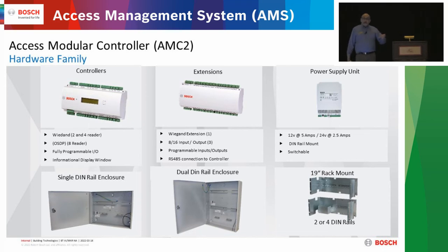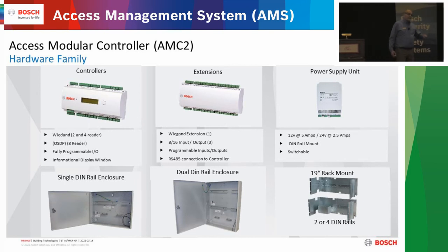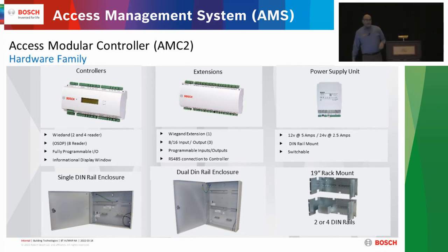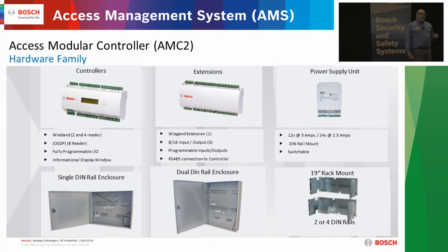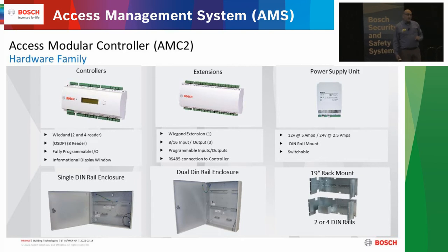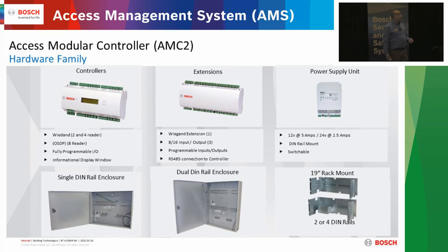On my outputs, they're not dedicated — I program them for how I want them to fire. The really cool thing is I can take a jumper on the back of this board and flip that jumper for any individual output, making that dry contact wet. The power supply is a 12-volt, 5-amp supply by default — flip a switch and it's now a 24-volt, 2.5-amp supply. I can put 24 volts into that control board, so my output is now putting out 24 volts to that lock set while still sending 12 volts to my reader. I can have a dry contact sitting right next to a wet contact — very flexible.